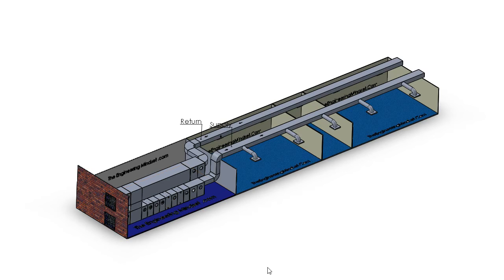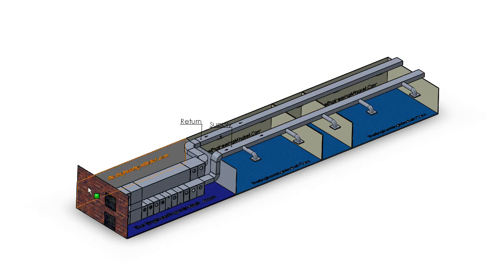The fans will also run at 100% the entire time this system is running, although you could fit some VSDs — variable speed drives — to the motors and lock that in at a lower frequency to get energy savings. But otherwise, converting this system to a VAV system is going to take a lot of time, effort, and modifications to the controls. But you get what you pay for — the CAV system in this basic form is very cheap and easy to install.